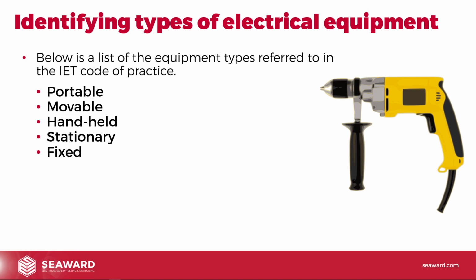Fixed equipment. Now, fixed equipment is generally equipment that's intended to be fixed in a set location. So this could be something like a hand dryer, a water boiler, an electric radiator or something like that. Now, the name has got taken really to mean equipment that's permanently connected to the fixed installation. Now, that can be taken as true. We've talked before in previous sessions that it doesn't really matter whether this equipment is connected by means of a plug or socket or whether it is connected directly to the fixed installation. These categories still apply. Fixed equipment is generally something that's fixed in a set position, i.e. screwed to the wall or screwed to the floor. So maybe on a plug and socket, maybe hardwired, but fixed equipment is something that's fixed in a permanent position.